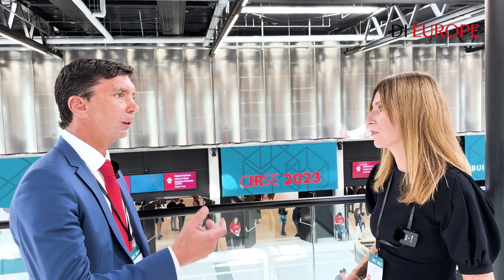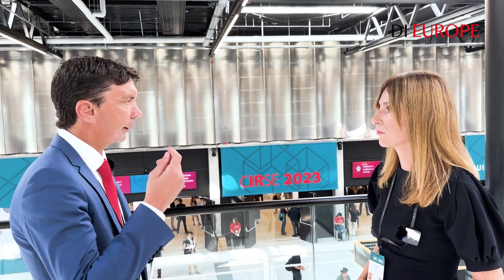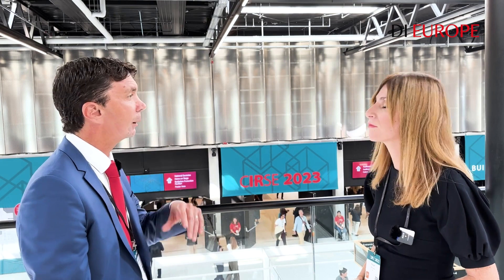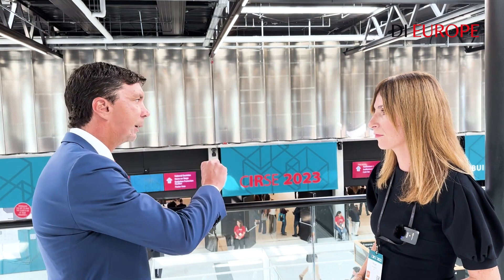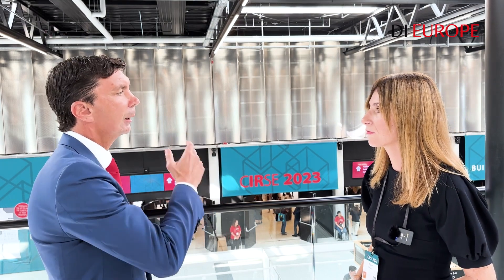Why cardiology first? Is that because they represent most of interventional procedures? Well, this has to lie on how innovation is driven within our organization. What we do is try to provide solutions that help healthcare professionals. When you talk with cardiologists, they are always questioning or willing to provide better image quality, lower dose, and real-time visualization, which is an important aspect. So we came up with a solution combining real-time artificial intelligence denoising capabilities, providing greater image quality as well as lower dose. And this is what Alphenix Evolve is doing.